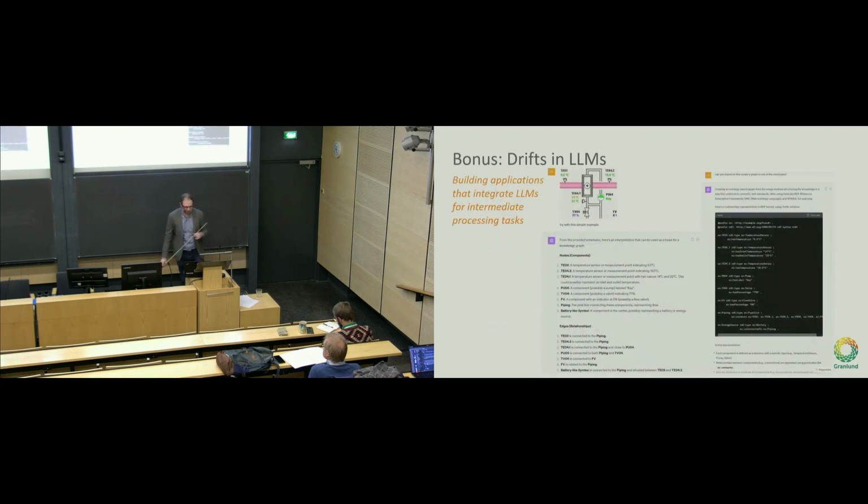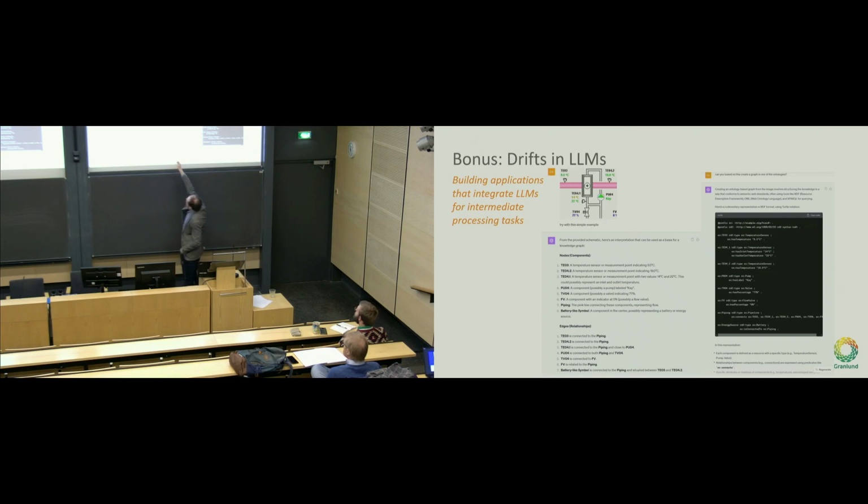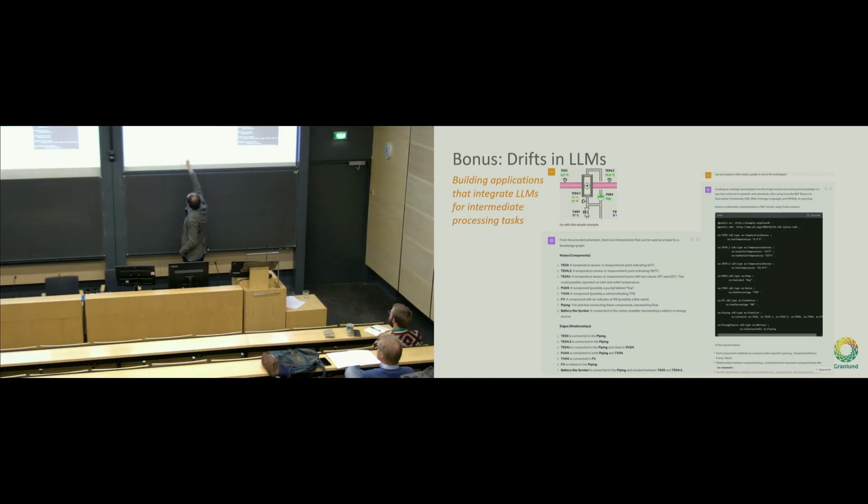So why is this useful? This is one idea that we have for one application for us. This was just a small trial, but this is a small image from the schematics of air handling units in ventilation systems. This is basically a heating coil, and then there's a valve, there's hot water around, and in the pink thing there's air coming. So air goes through, heats up and goes to the room. And there are sensors and valves to control that.